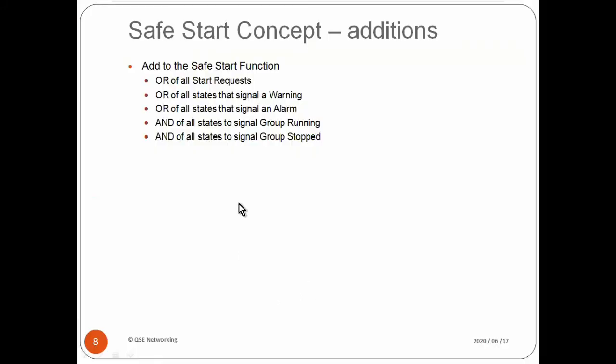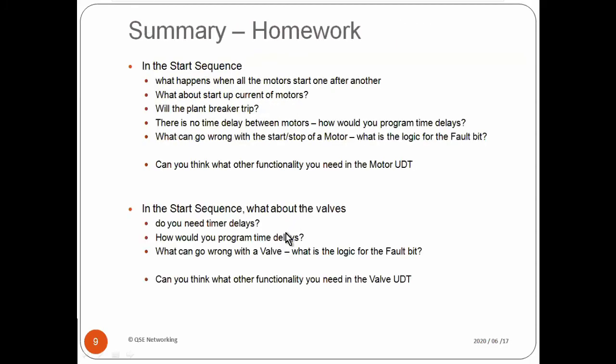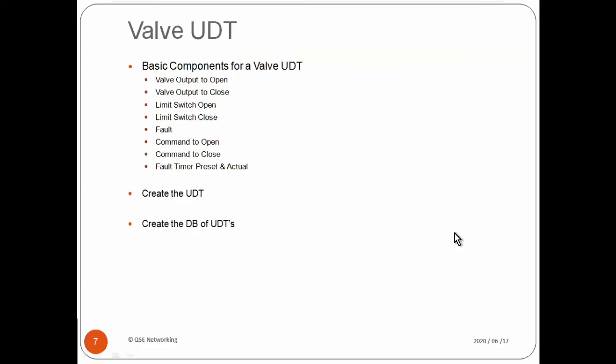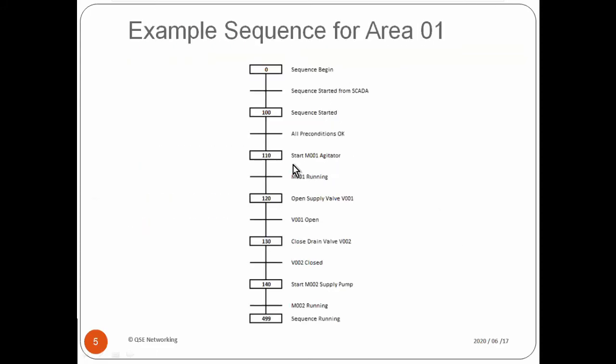Okay, so that is all of those functions that we've done there. Very simple little lesson today, or session. We have in the start sequence, just for you to think about, what would happen, like literally this sequence now. What is going to happen the moment this motor starts? Technically, the moment the output comes on, within milliseconds, the contactor will close and we'll get a run feedback. The valve will open. Okay, this one is nice because the valve will take a second or two to open. And this one, then we'll start the motor. Say the safe start period is still active, so this motor will start.